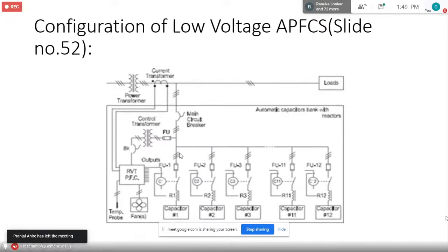Generally each capacitor will have a fuse. Actually, there will be an isolator, then a fuse, then a contactor, the series reactor, and the capacitor. The contactors switch it in and out. And this is your automatic power factor controller. It is sensing the current and voltage of the load, and thereby it determines the power factor. Then, depending on how many kVA are required, it will switch the contactors in and out.